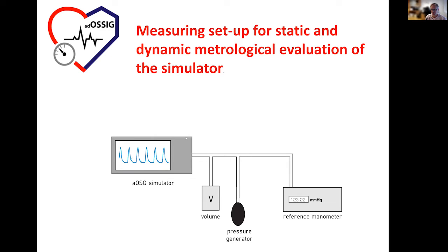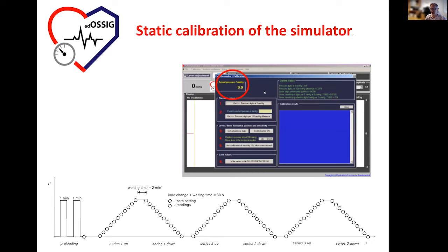We would plug the simulator to a residual volume, to a metal box with different volumes. And this line here is the tubing. So the pressure generated by the simulator would go into the volume here, into the pressure generator, and into the reference manometer. One important part is the pressure generator, either a manual one, like this rubber ball, or an electronically controlled device, like a calibrator of some sort, or any sort of pressure generator. And then what we need is a reference pressure transducer, accurate enough for all this. So basically what we did in static calibration, we were calibrating in a classical way the pressure transducer of the simulator. And this is the front panel of the simulator.